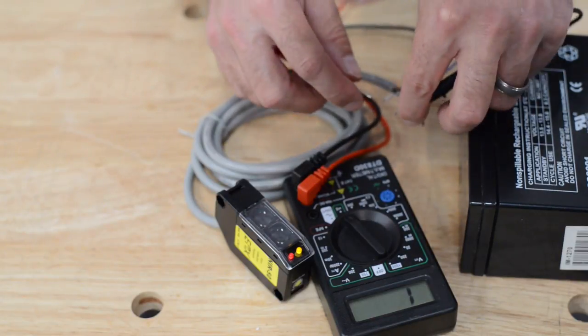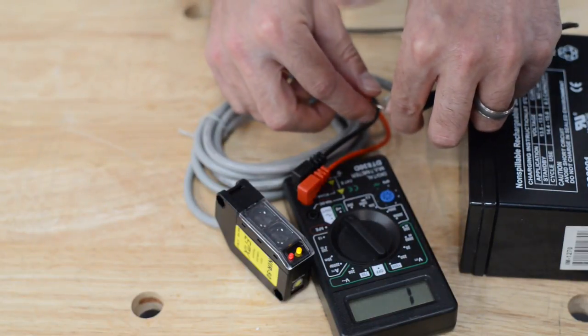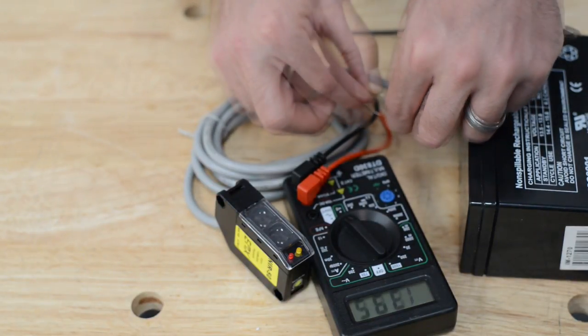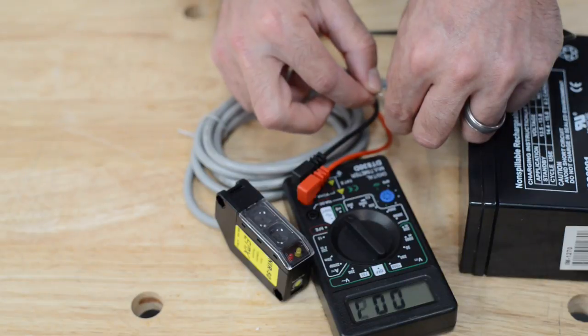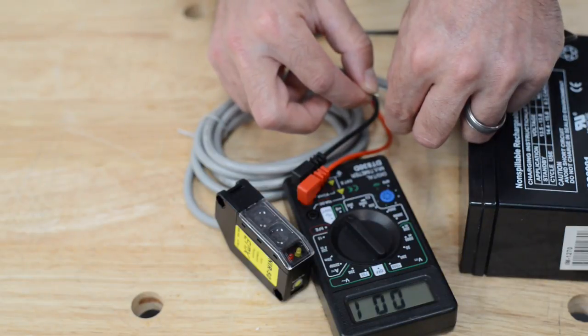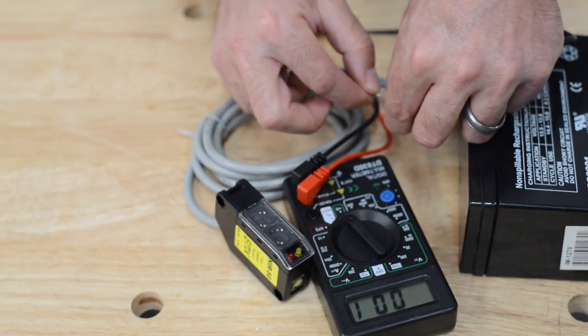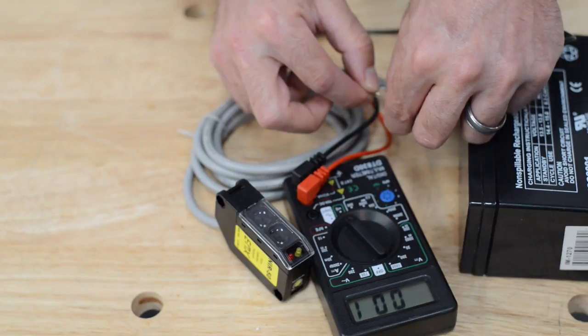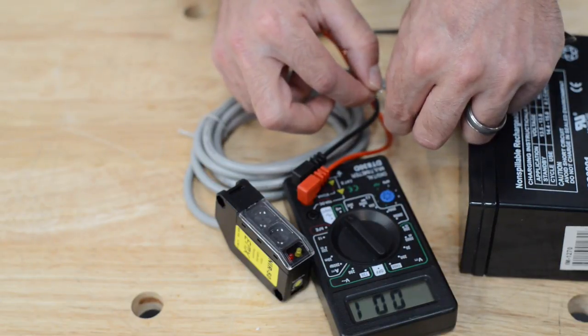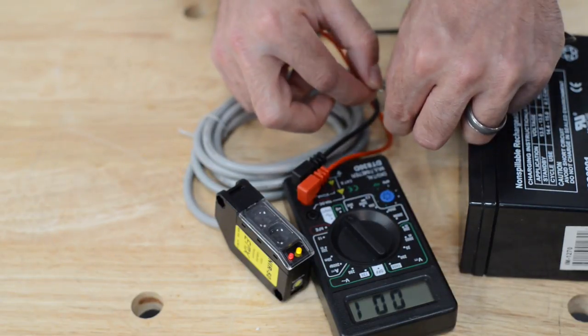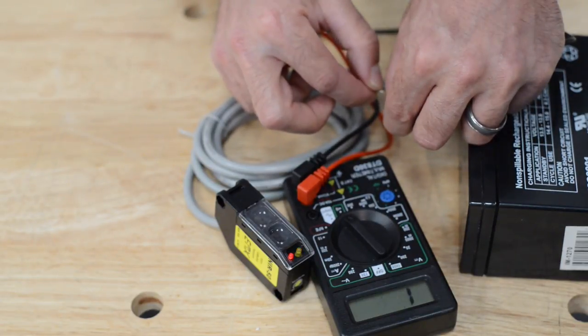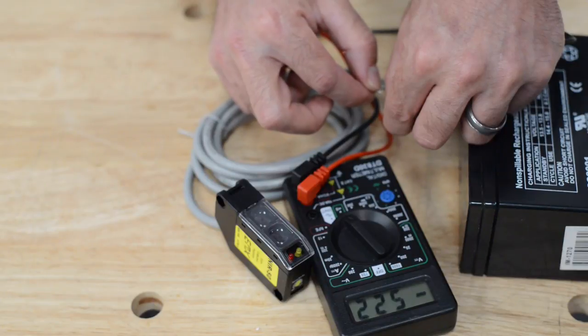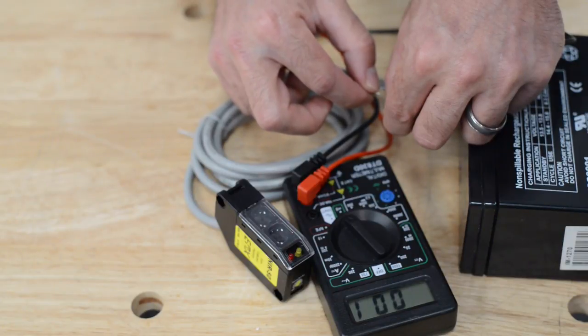One last thing I could do to test this out. When the beam is disrupted, I now have continuity between the white and the gray, which is correct. When the beam is disrupted and normally open, then becomes a closed circuit and you gain continuity.